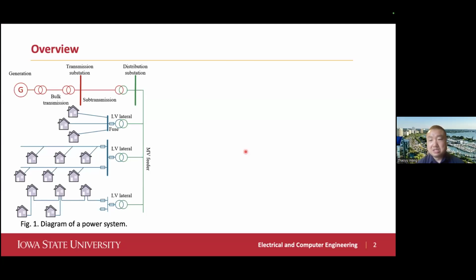I think most of the audience knows that we have the generation part, the transmission part, and it goes to the sub-transmission part, and then to the distribution part. Distribution is our focus today, and anything below 35 kV is considered the distribution system in the United States. It has a primary, we call it a medium voltage feeder. It could be 35 kV, it could be 13 kV, it could be as low as 2 kV for some very old systems, and we call this a primary feeder. We also have the secondary, you can call it a network, but I would not say it's a network. It's more like a radial, star-like, drop lines system, so we call it a secondary system. In European countries, they call it a low voltage system. After the distribution transformer, it goes to 120 and 240 volts.